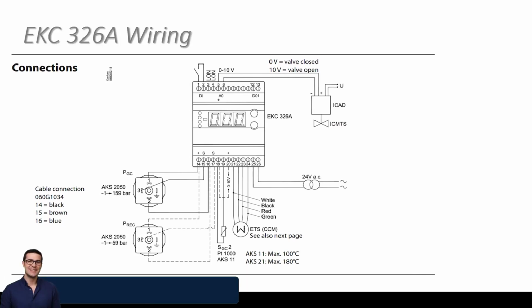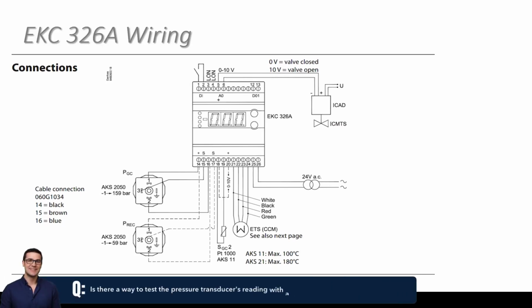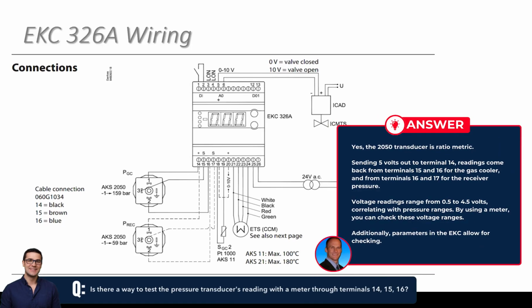Yeah, exactly. Is there a way to test what that pressure transducer's reading with your meter through 14, 15, 16? Yeah, so the 2050 here, this is a ratiometric transducer. The way that works is you've got a terminal 14 here where we would send 5 volts out to the transducer, and then you get for the gas cooler 15 and 16 back, and for the receiver pressure we're on 16 and 17.